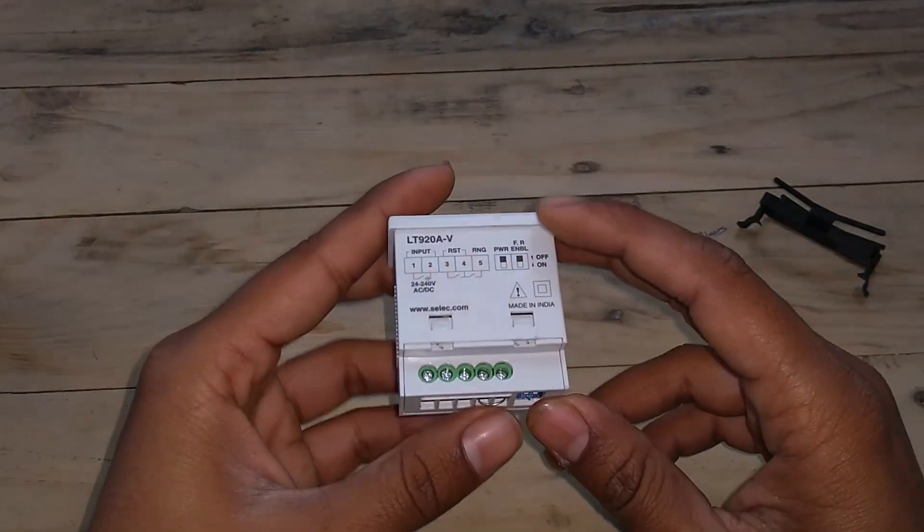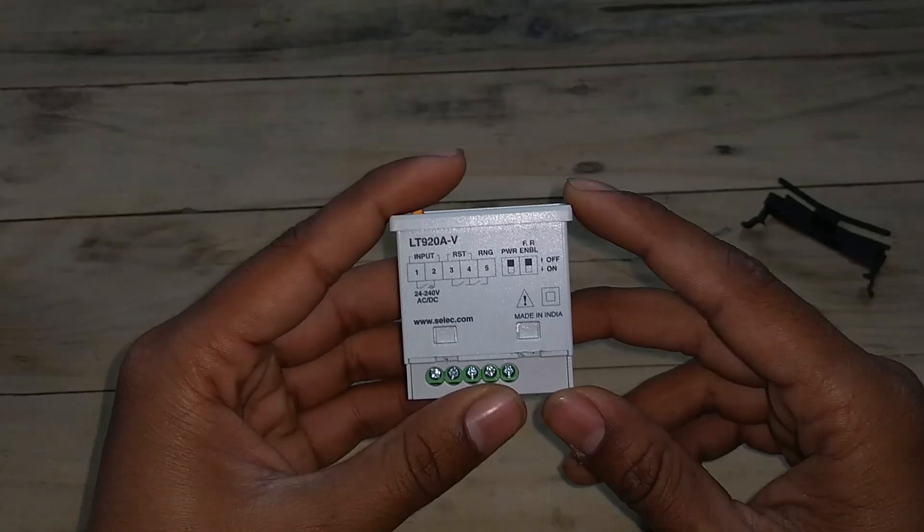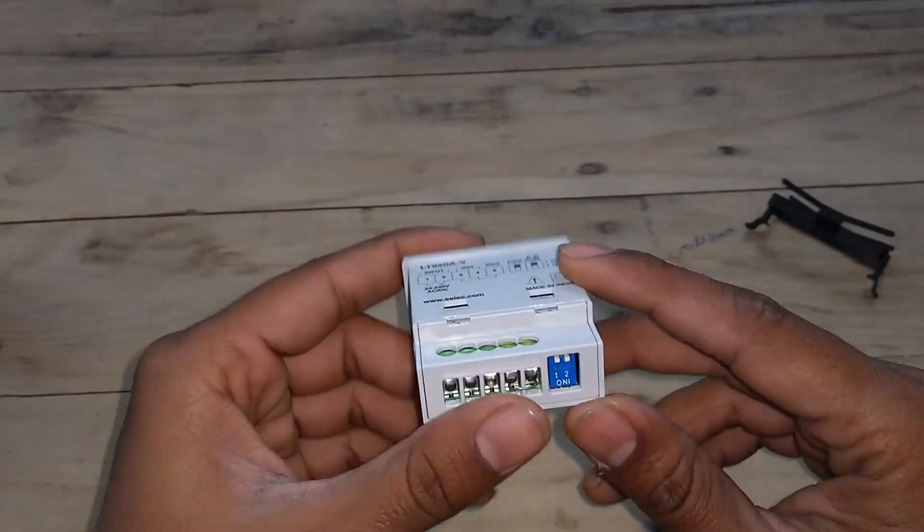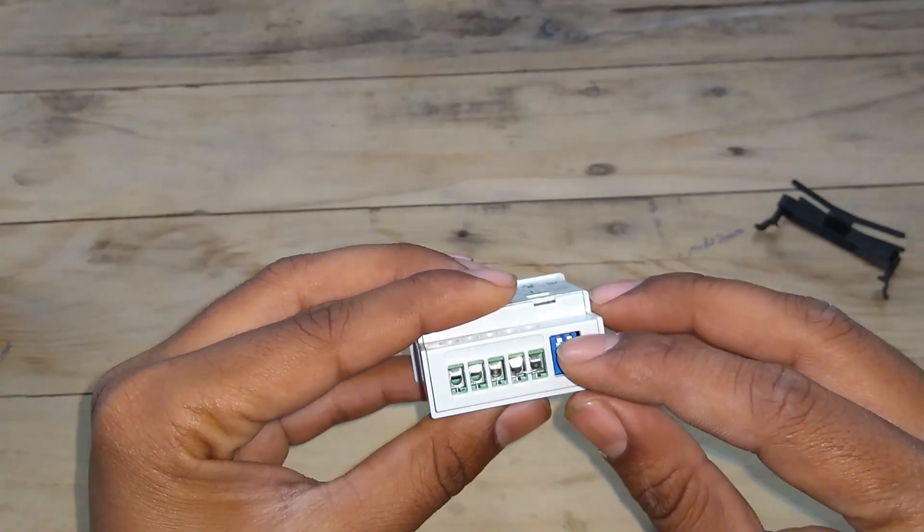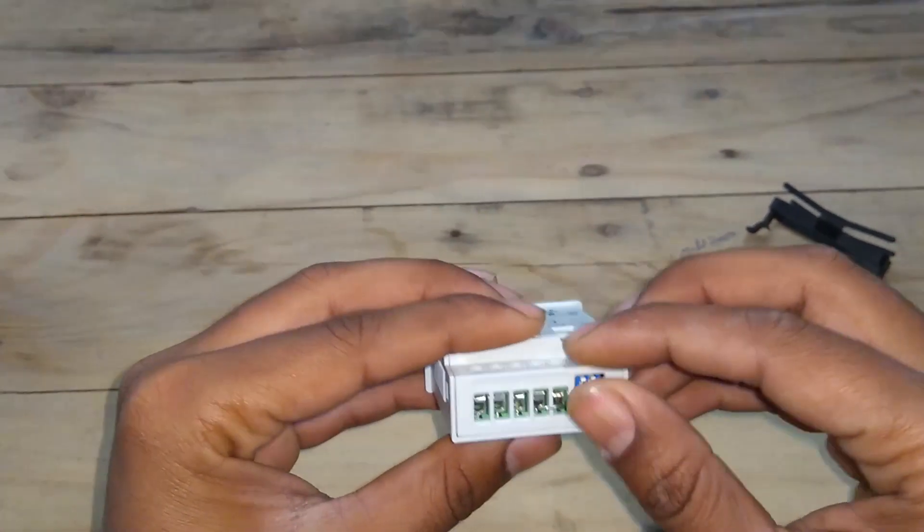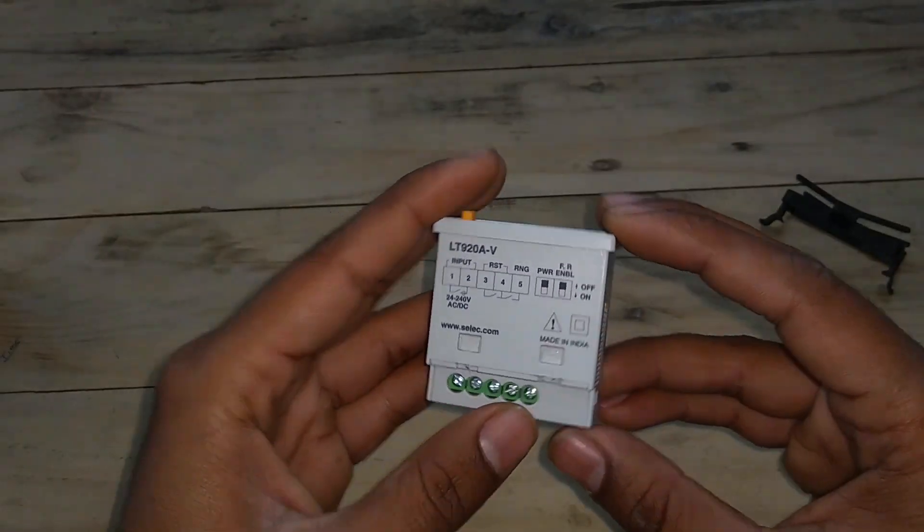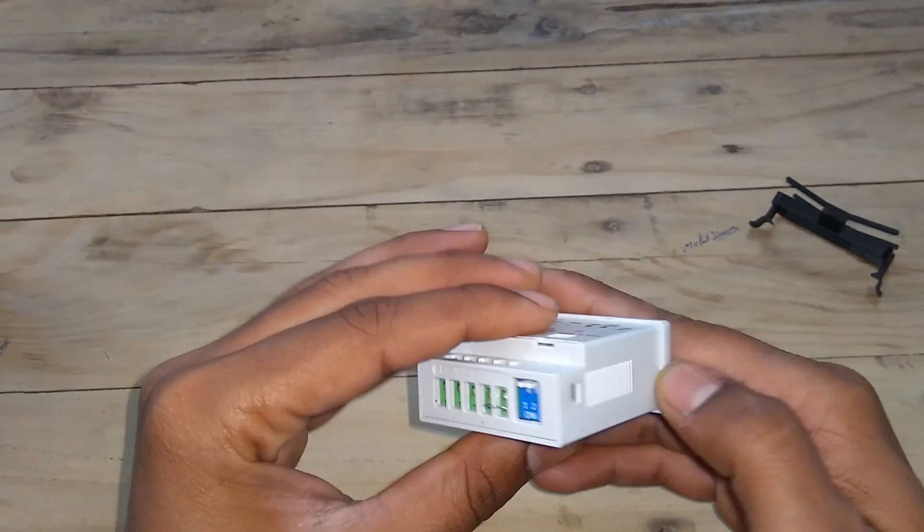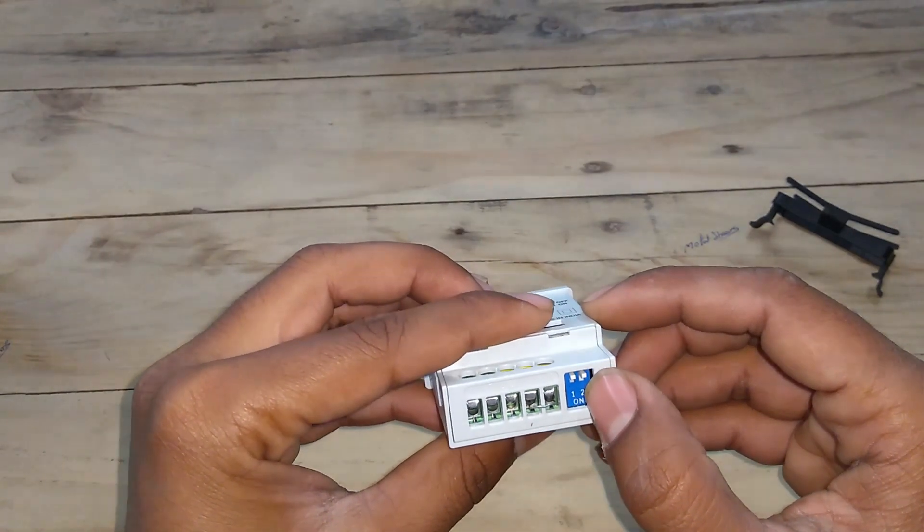Other than that, there are two DIP switches. One for power and one for FR enabled, which means if you want front reset enabled, then you have to turn on the second switch, which is FR enabled. If you want to disable the front reset button, this one, you can disable this number two DIP switch.